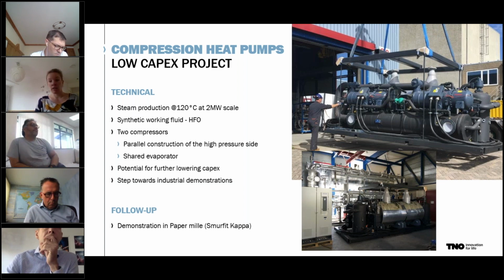This heat pump that you see here is being towed in, and on the lower picture you see it installed in the lab. The black part is the heat pump, and behind it, the aluminium silver colored part is the actual infrastructure that is going to generate waste heat to operate the heat pump. With this heat pump, we're going to produce steam at 120 degrees C at 2 megawatt scale. We're using a synthetic working fluid, an HFO.